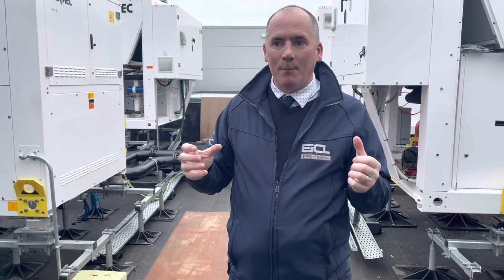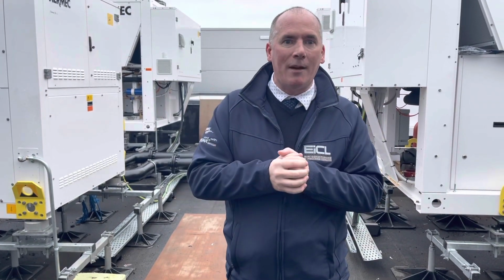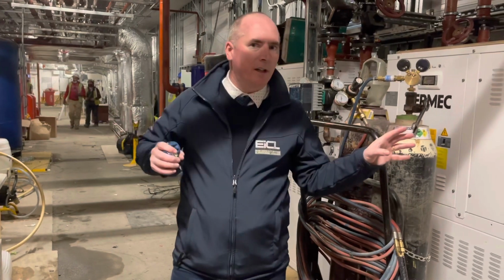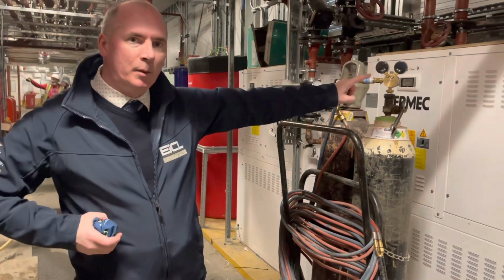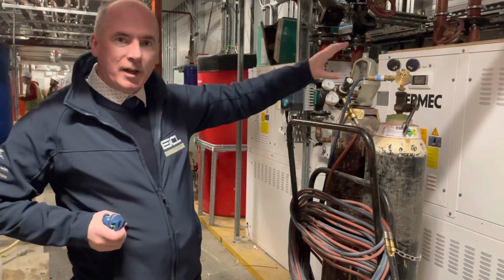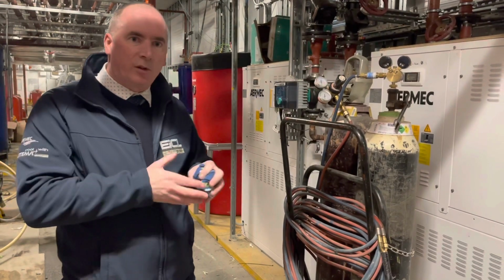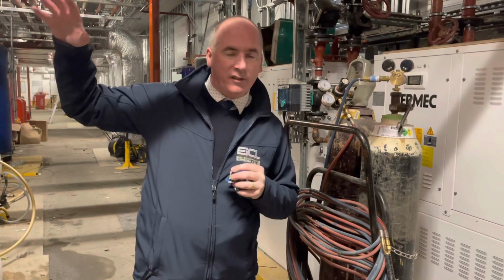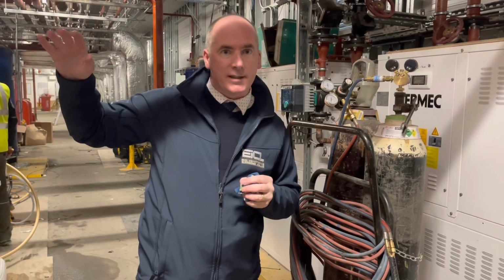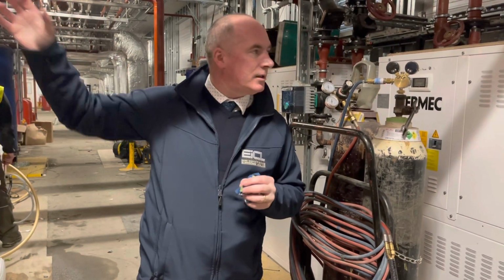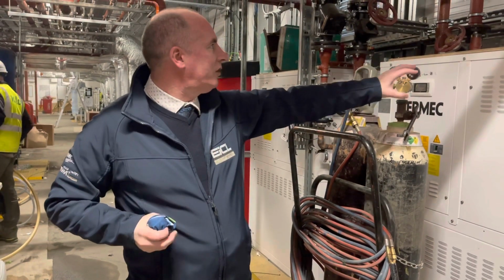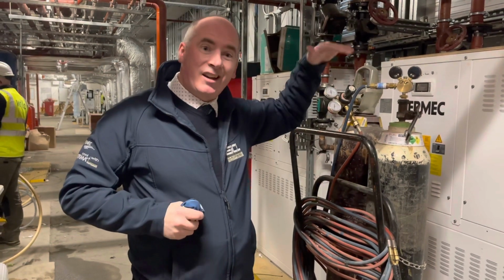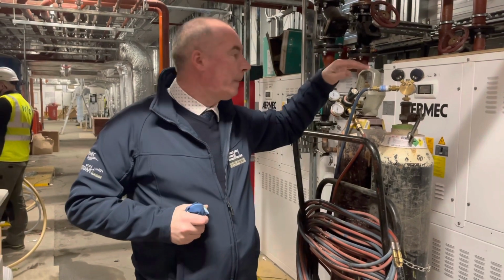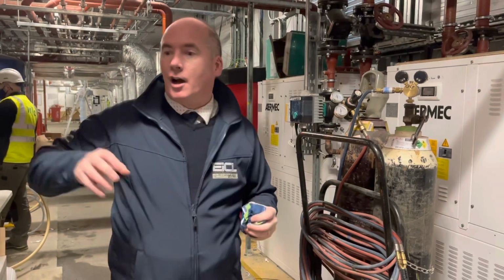So that's it. We'll do a quick visual inside just to show you what we have in there. Okay, so we're in the plant room here now, and we can see we have the two WWBs. So these are the water-to-water booster. These are being fed by the LTHW, your 45-40 degrees C temperature from the heat pumps outside. They're coming into these, they're boosting the temperature up. They can go up to about as high as 80 degrees C. They then in turn are feeding the calorifiers.